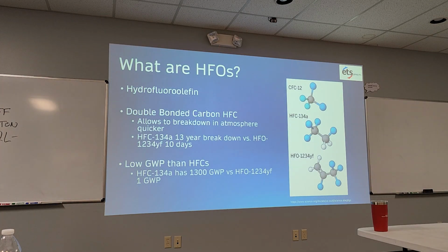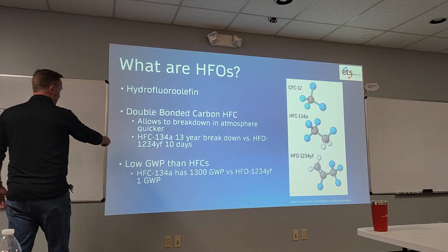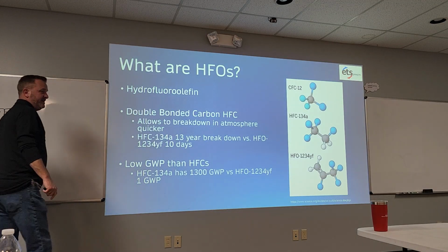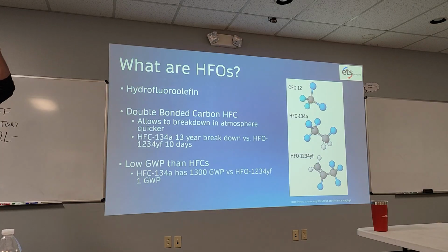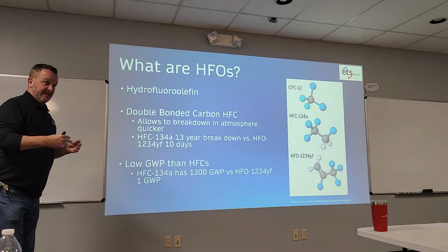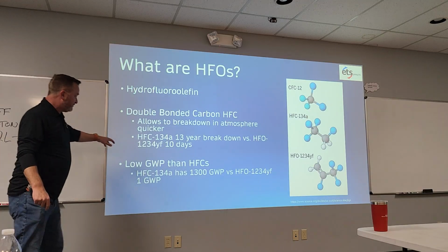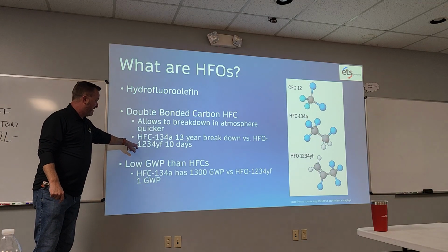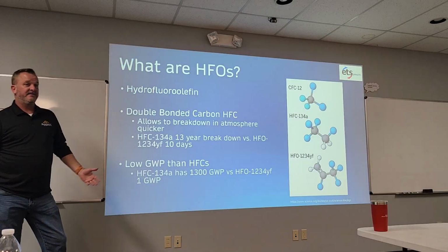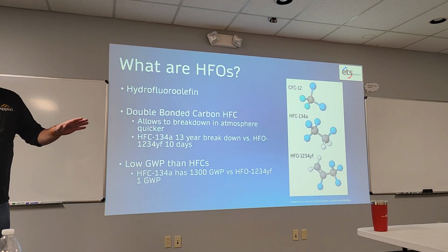So the way you look at it is each refrigerant molecule has a lifespan, right? So R-410A leaks out of the system, it goes up in the ozone layer and supposedly does its damage. Again, I'm not a scientist, I'm not a chemist, but that's what it does. It's got a certain lifespan out there. So if we look at it, 134A right here has a 13-year breakdown. So it's gonna go up there and cause its issues, cause its damage. And then pretty much that's its life, right? Then it becomes inert. The swap out for that, the HFO, would be 1234YF, which is only 10 days. That's the drive for these refrigerants, plain and simple, all right? It's better for the environment.